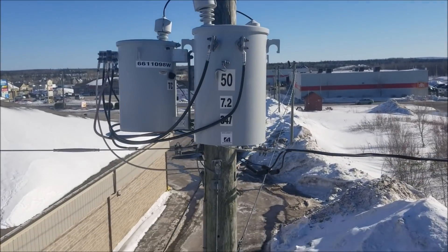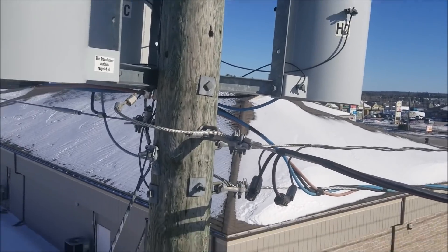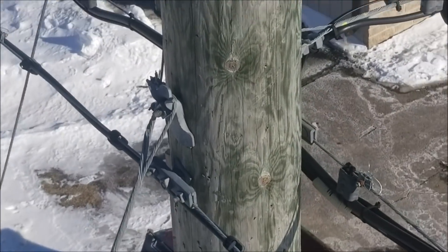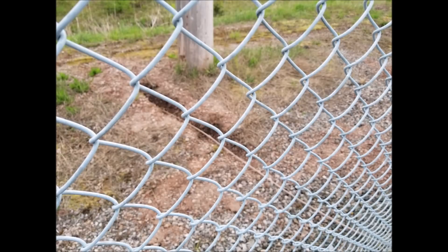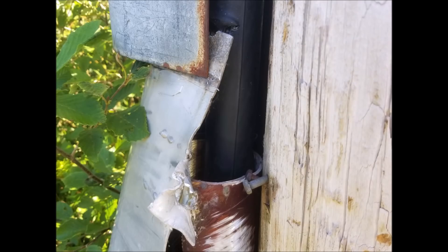As we and many other utilities use a multi-grounded system, whether it's the neutral or ground wire that's cut, it can result in a deadly difference in voltage. The returning current or even induced voltage no longer has a return path to ground or its source. So if you happen to be touching one of these wires once they're cut, you may become the new path — with deadly results.